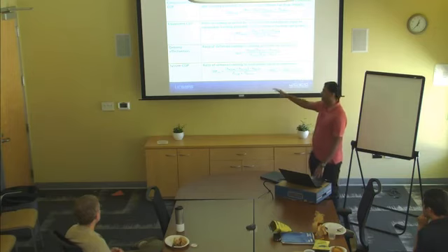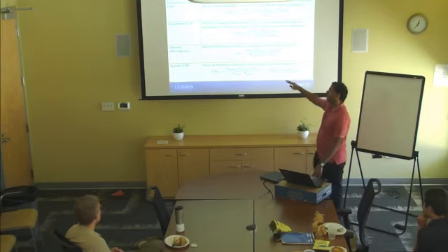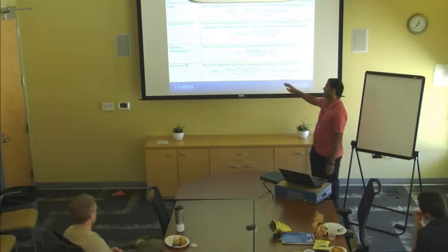And finally, the system COP, which you can think of as a combination of equipment COP and delivery effectiveness, the product of those two. So the ratio of cooling delivered at the grills to the total power input to the equipment.